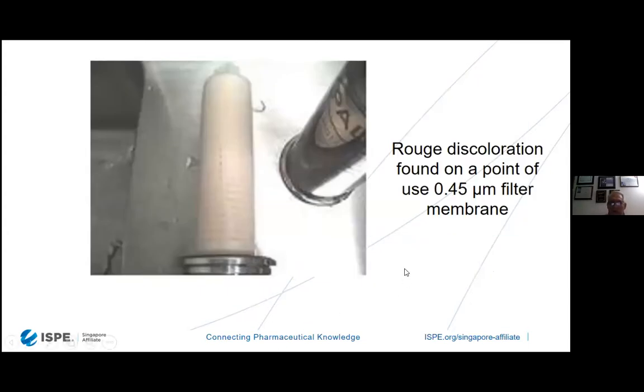Some people say, well, I put filters into my system and they're turning red. And I say, well, that's a good thing. And they say, what do you mean it's a good thing? Well, it means that it's taking out the particulates that are actually in the water. You can see over here, there's a pinkish, reddish color to this particular membrane, being a 0.45. Even WFI water systems can have membranes on them and filters. There is no law whatsoever. There is no guideline. There is no mandate that says you cannot have filters on a hot WFI water system. And if you want to put them there, you can.